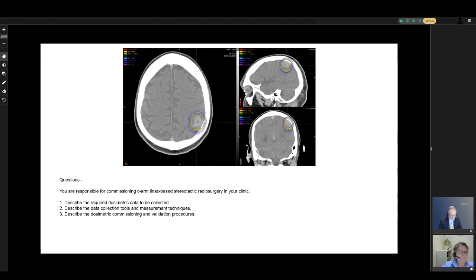Yeah, so you definitely want to do some end-to-end tests in a phantom. You can use something like a Lucy phantom. So this phantom, you need to somehow measure point doses, so it needs to house point dosimeters as well as films. So I would start with some simple plans. You verify point dose, and you do a gamma analysis on the film, and then you can move on to more complex plans. And then really at the end, I would recommend an IROC verification. So they send out these phantoms that have OSLDs in them, and then you make a treatment plan to some specifications that IROC gives you, and then you send them back, and they then go and measure the point dose as well as the film dosimetry, and they send this back to you.